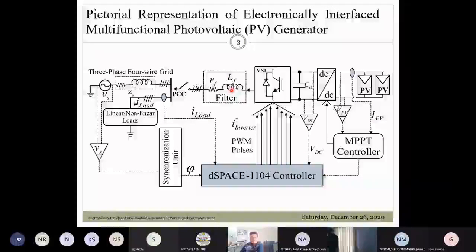It is important to mention that the effectiveness of this inductive filter largely depends on the grid impedance. Therefore, it is of prime significance to take special care while implementing and designing this interfacing inductor. The breakers connected at the AC terminal of the VSI output are primarily responsible for protecting and isolating the inverter assets during transient faults.